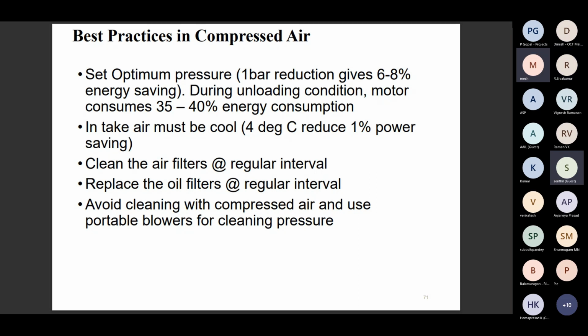we can definitely go with a VFD. Also, the intake air must be very cool. Especially in foundry areas, there is a lot of heat, so the utility room must be very clean. Every 4-degree reduction gives 1% power saving. Clean the air filters at regular intervals and replace the oil filters at regular intervals. Avoid cleaning with compressed air and use portable blowers for cleaning. An electrical blower can be used for cleaning wherever possible.